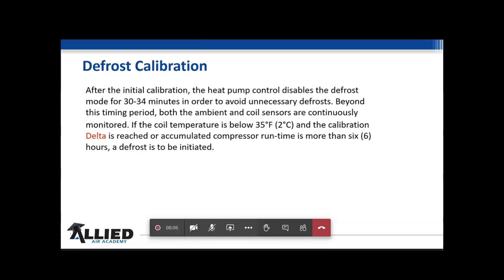So after the initial calibration, the heat pump control disables the defrost for 30 to 34 minutes. I have no clue why it's 34 minutes. That's what it said in the documents. But it's going to avoid unnecessary defrost. So what this is saying, after we're calibrated, I'm not going to let you go into a defrost, regardless if the conditions are right, for at least 30, 35 minutes.